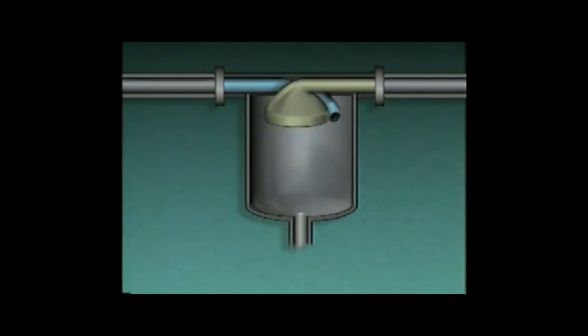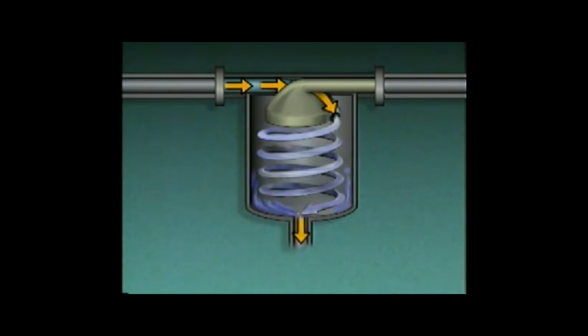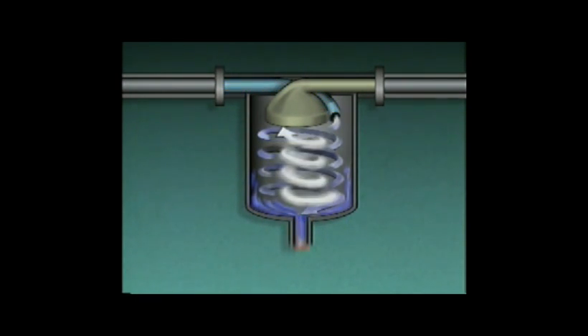As moist gas enters the demister, it begins spinning. Because liquids are heavier than gases, centrifugal force causes liquid to separate from the gas and hit the shell. The liquid runs down the shell and out through the liquid outlet, while the gas enters the collector and leaves through the gas outlet.